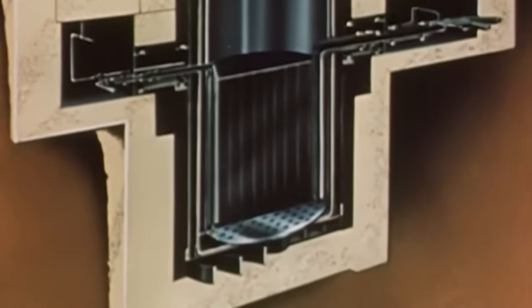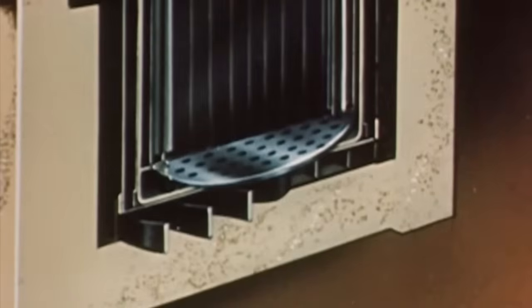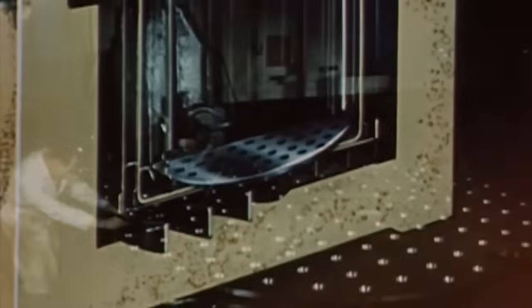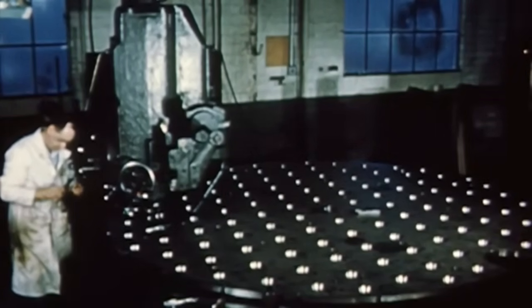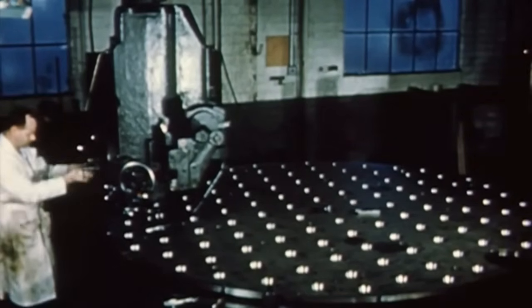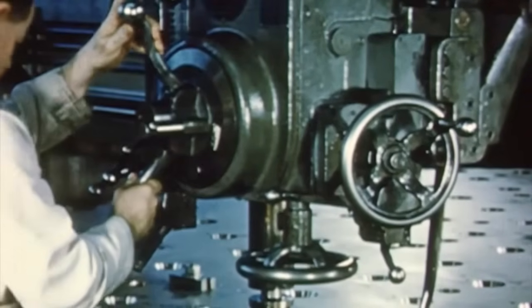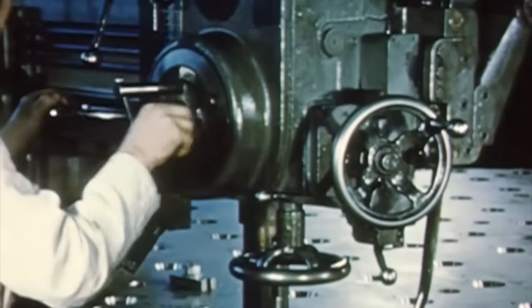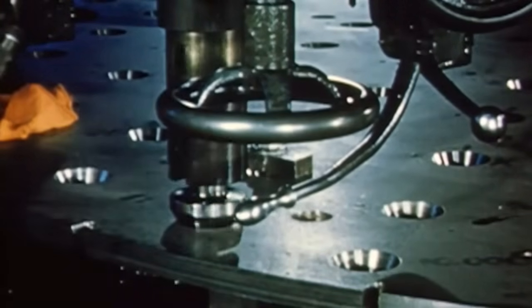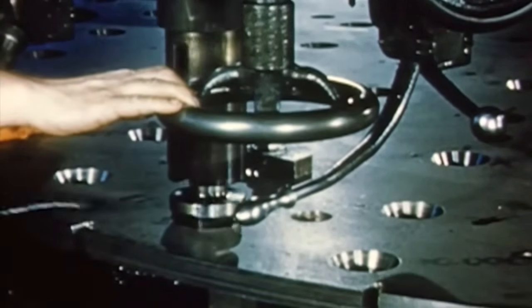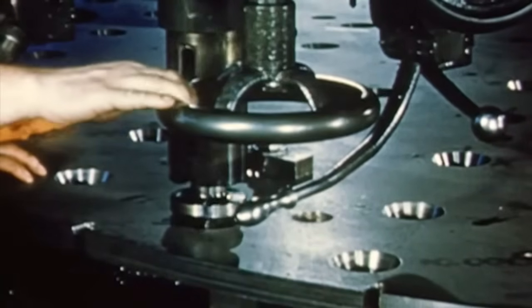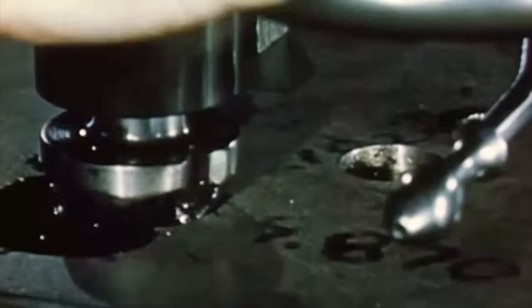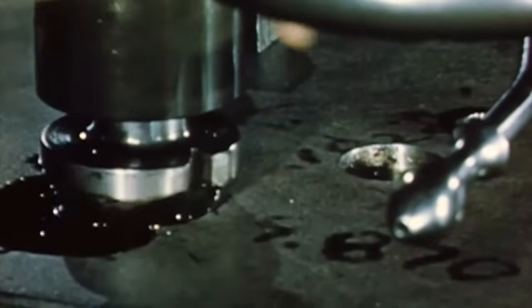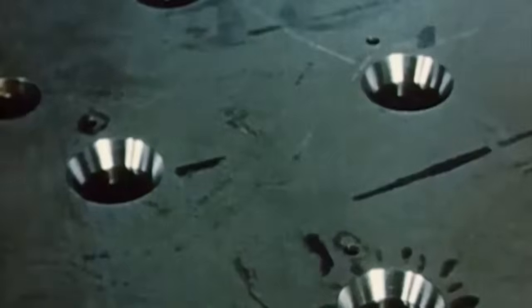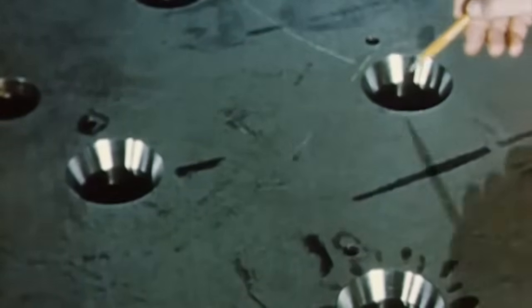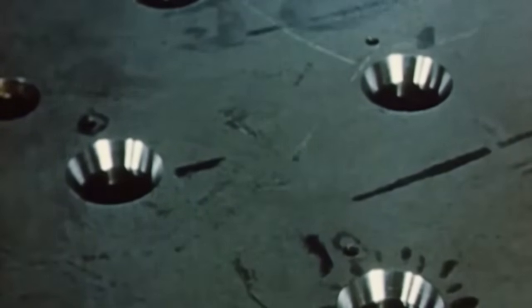A grid plate near the bottom of the core tank supports and locates the moderator assemblies. It was fabricated from type 304 stainless steel and is 1.5 inches thick. The smooth finishing of the moderator can spacer holes is shown here. A pedestal at the bottom of each moderator can fits into these holes to support the can and position it precisely. These holes space the lower ends of the moderator cans and fuel elements on an 11-inch triangular lattice.